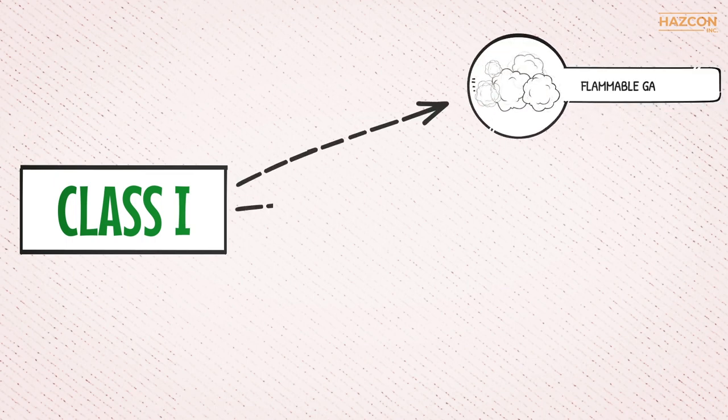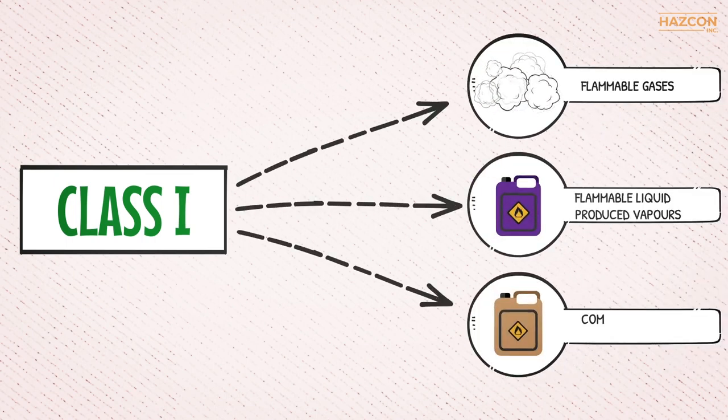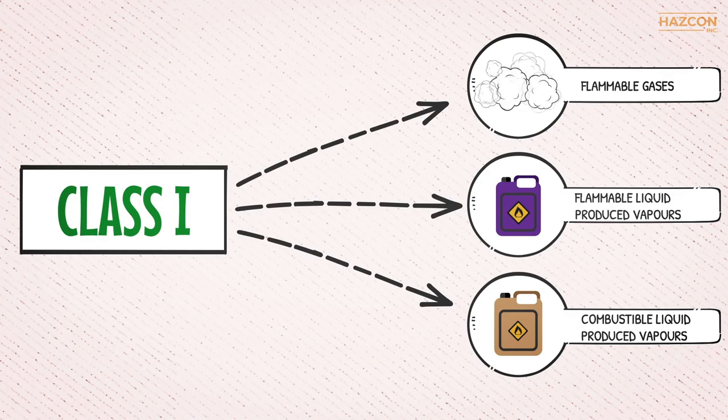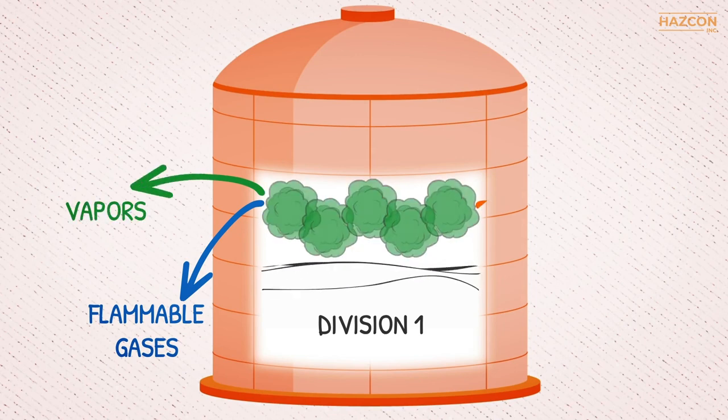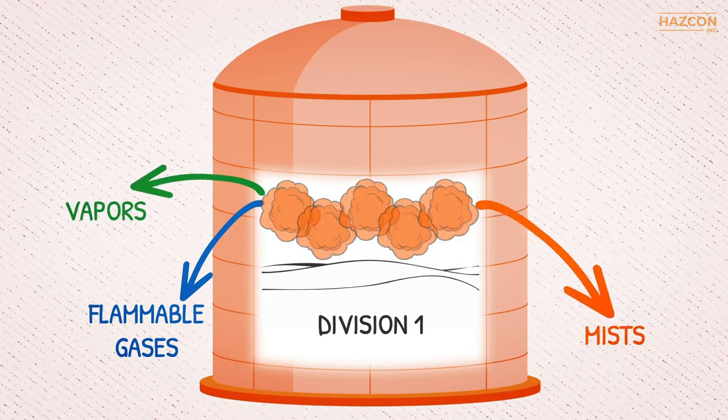Class 1 means that the location contains flammable gases, flammable liquid-produced vapors, or combustible liquid-produced vapors. Division 1 refers to an area in which these dangerous concentrations of flammable gases, vapors, or mists exist continuously for long periods of time or frequently under normal operating conditions.